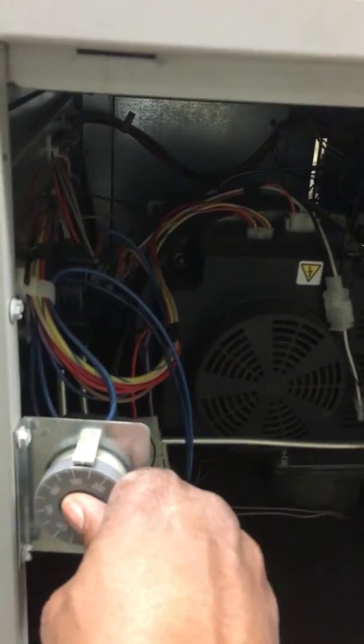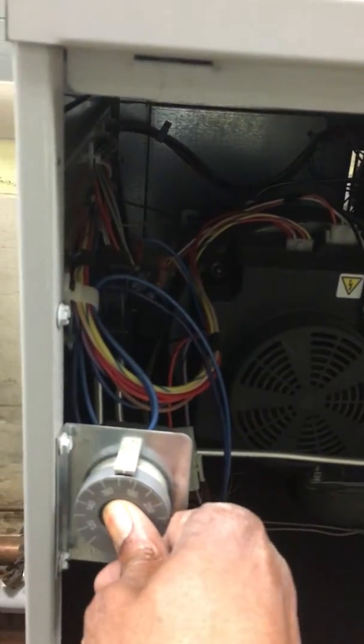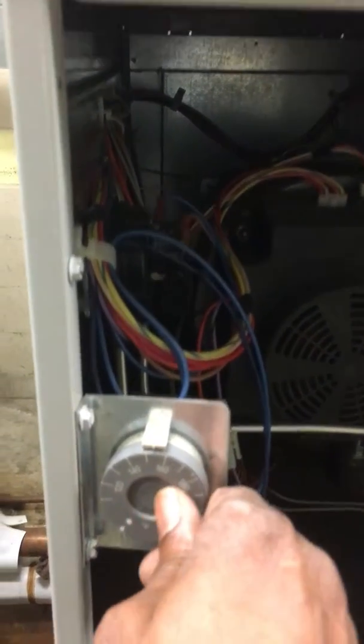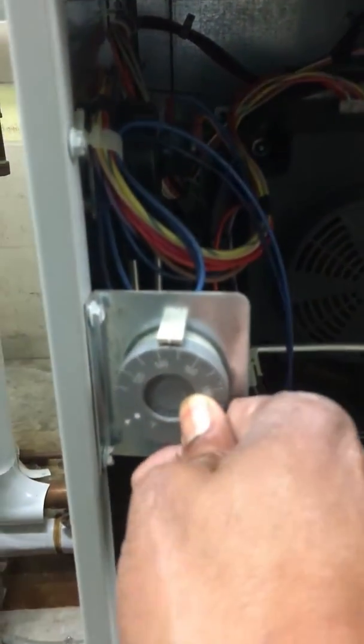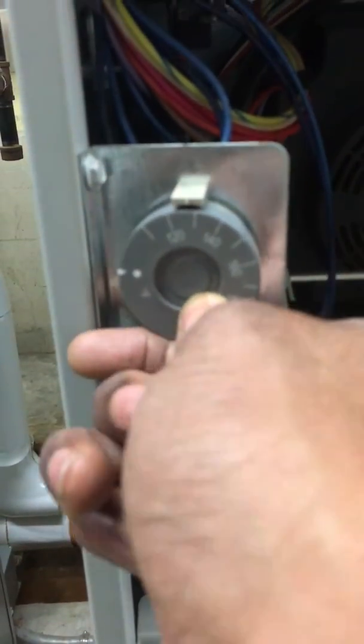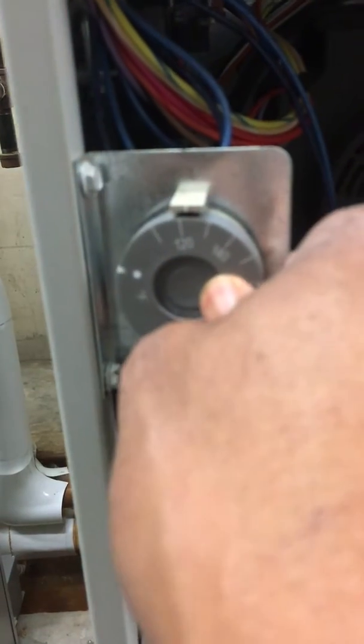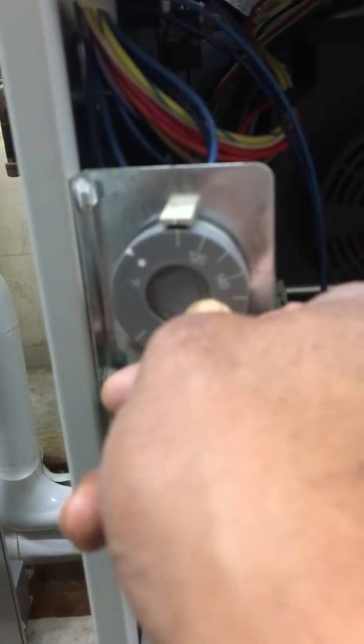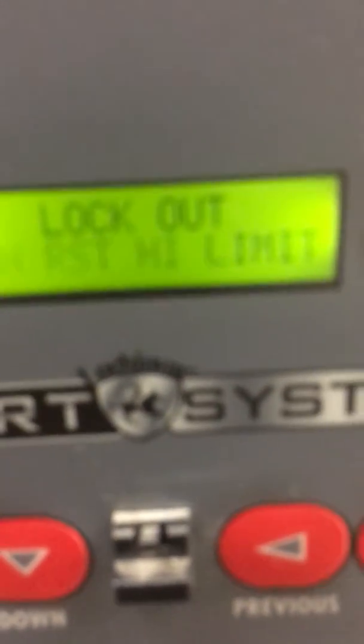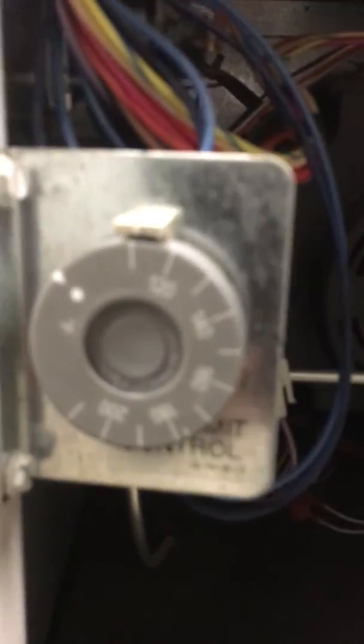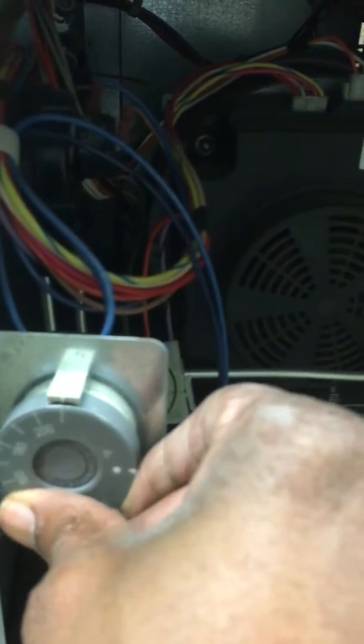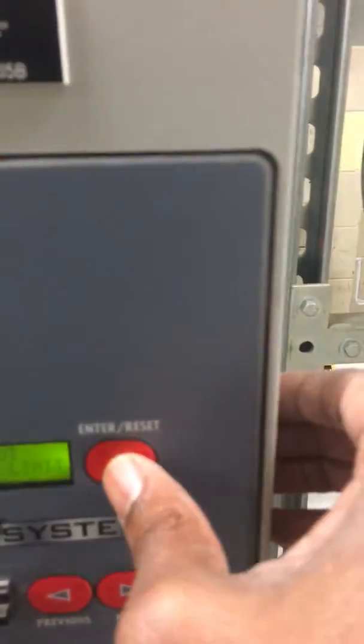So watch, you hit click. Watch, there it goes. See, we have a lockout. So that means that it stops the water heater from going up. So that test, the high limit test works. So I'm going to push it back up until it's 220 and go ahead and reset.